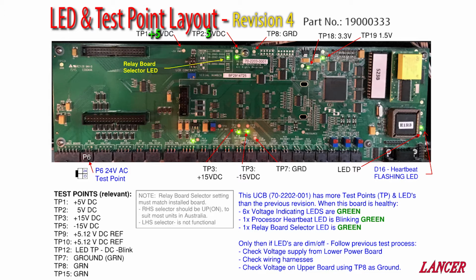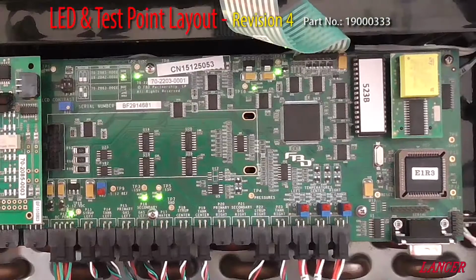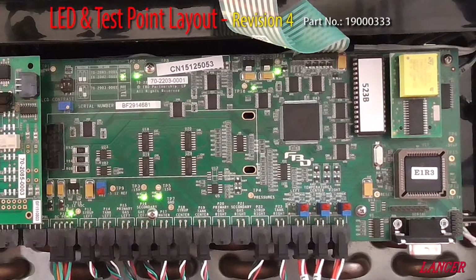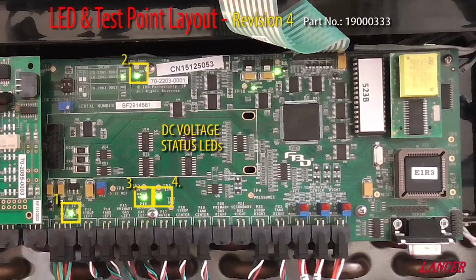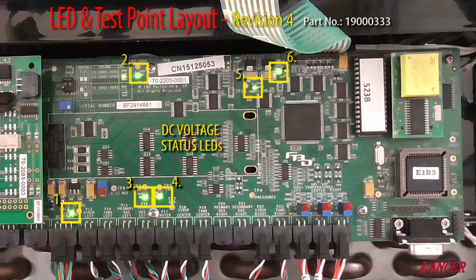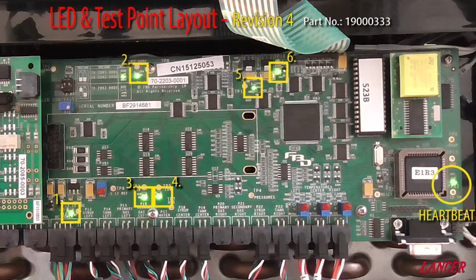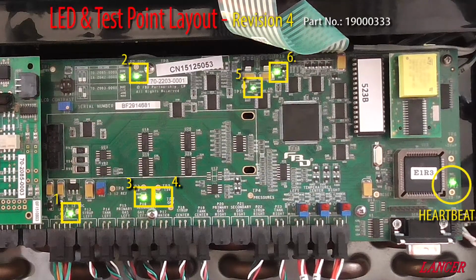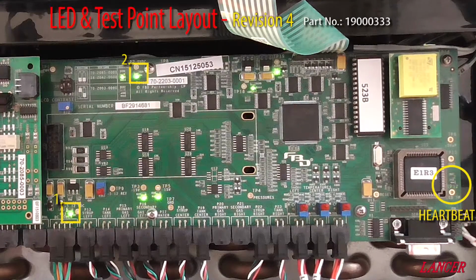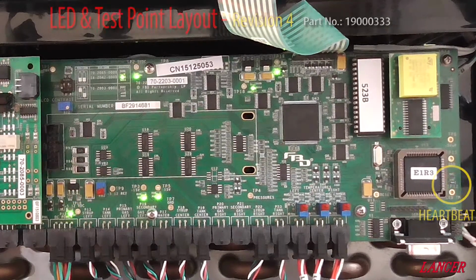5 volts DC is used to supply the coils on the relay board and the logic processor. 15 volts DC is to control the sensors. And 24 volts AC is switched by the relay board to energise the LEDs, the contactor and the solenoids. The important test points have voltage indicating LEDs. There are now 6 LEDs to assist with voltage confirmation, and there is still 1 heartbeat LED indicating that the processor or software is functioning correctly. Each of the test points are labelled and are much easier to access.